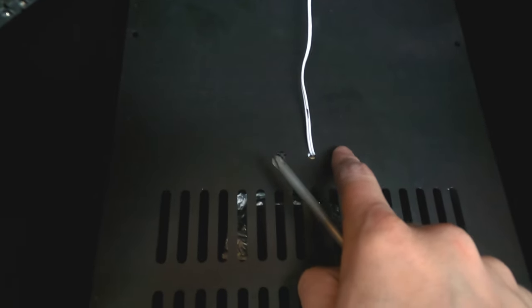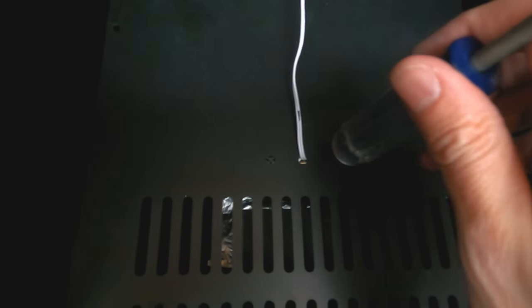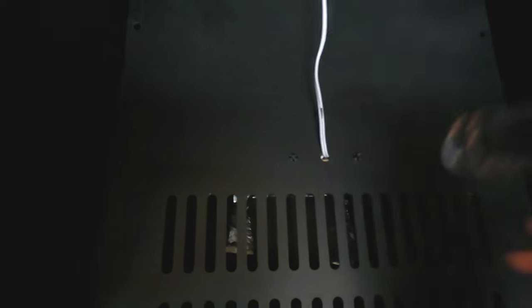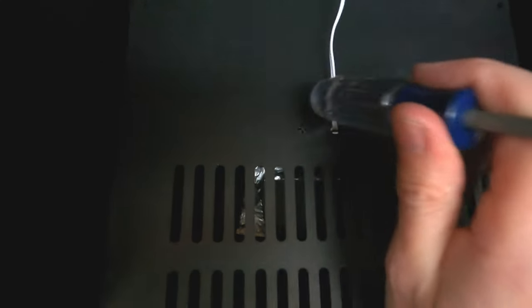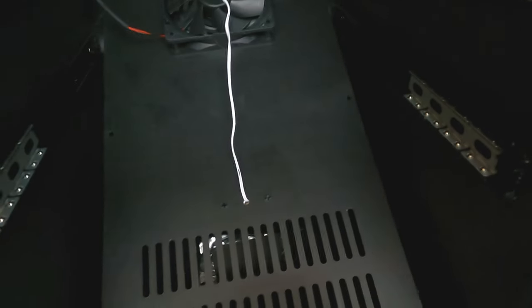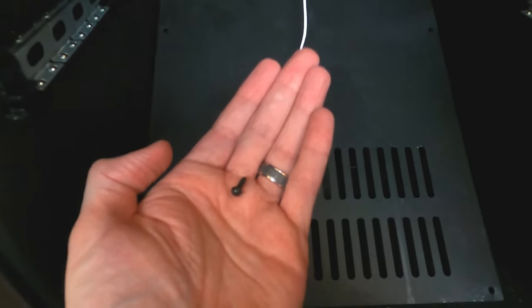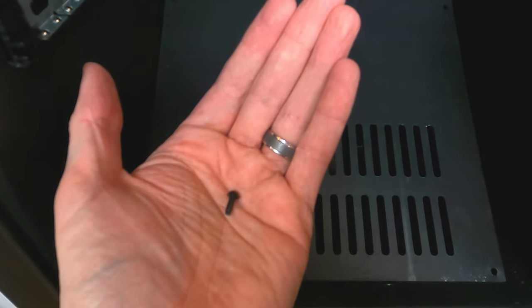Now, obviously we'll want to kill the electricity and whatnot when we do that, but it's at least good to be able to pull this apart because we can see that we're actually getting a little bit of frost over here on this, which probably means that it might be spending a little bit more time in cooling than it should, because it's starting to take the air, which is really only supposed to be in like the 40s for this, and bring it down far colder than that. One little zip tie that kind of holds all these wires together back here. So I just snipped that, and now what we're going to do is basically take these little pressure sensitive things, and in my infinite wisdom, I'm just going to tap them real fast with a screwdriver to pop them out, and then they should pop out on the front side like that. At least I got one out. I have to put the camera down to get the other out, but they're just these little pressure screws or pressure rivets, I guess.